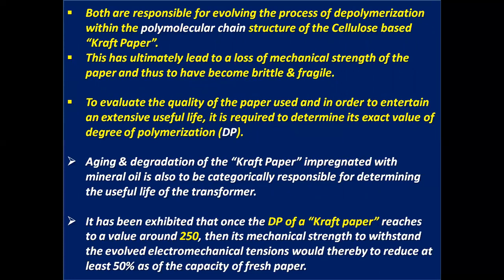Both acid hydrolysis and oxidation are responsible for evolving the process of depolymerization within the polymolecular chain structure of the cellulose-based kraft paper. This ultimately leads to a loss of mechanical strength of the paper, causing it to become brittle and fragile. To evaluate the quality of the paper used and to ensure an extensive useful life, it is required to determine its exact value of degree of polymerization, what is called DP.